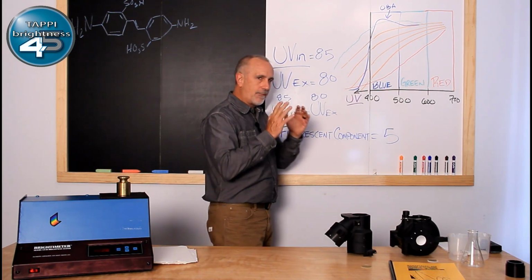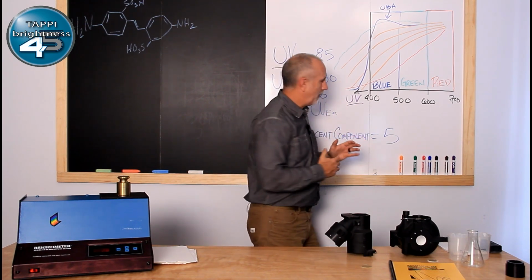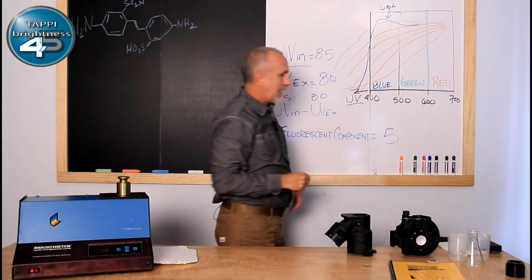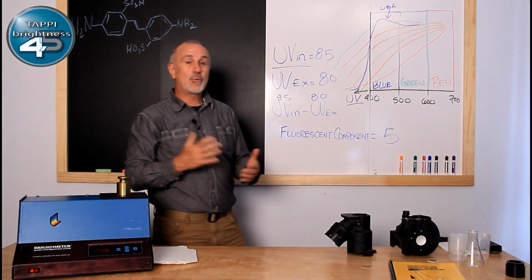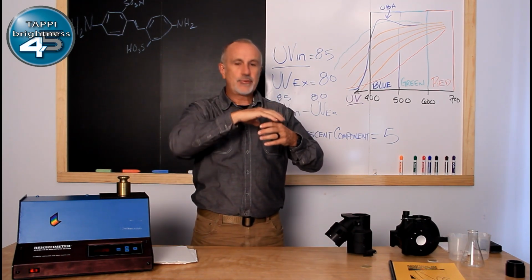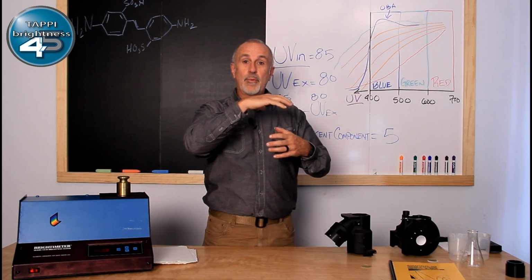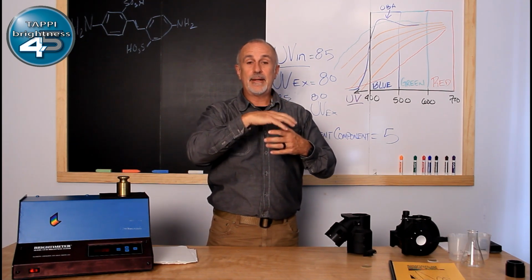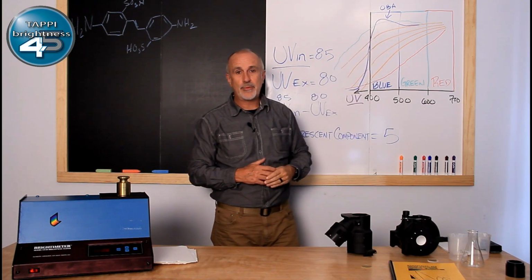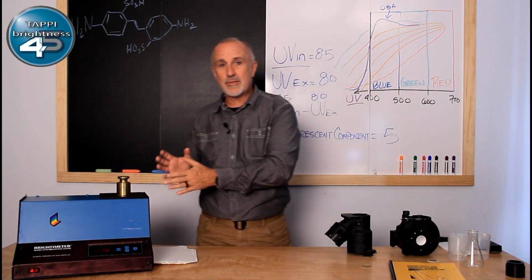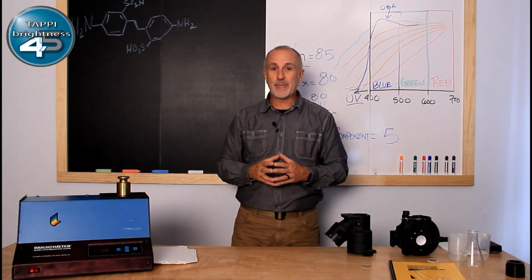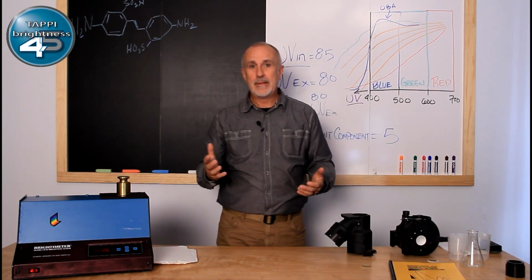Because, back from our brightness videos, brightness is just looking at this blue region of the spectrum, and if that's where it's looking, that's where the OBAs are doing their most work. And so as we add optical brightener, and we're seeing that improvement, what we're seeing is an increase in blue reflectance in that sample. So as it turns out, the brightness instrument, even though it wasn't designed to look at optical brighteners, is a perfect instrument for doing the evaluation and the management of an optical brightener.